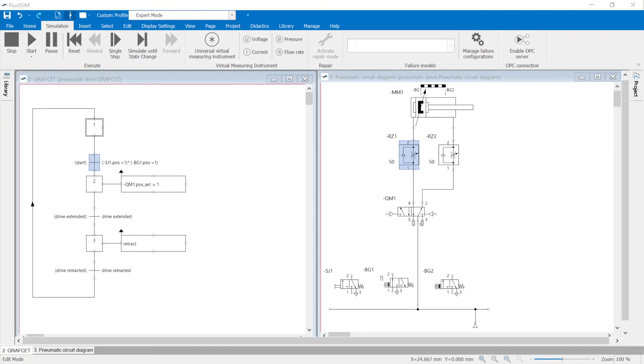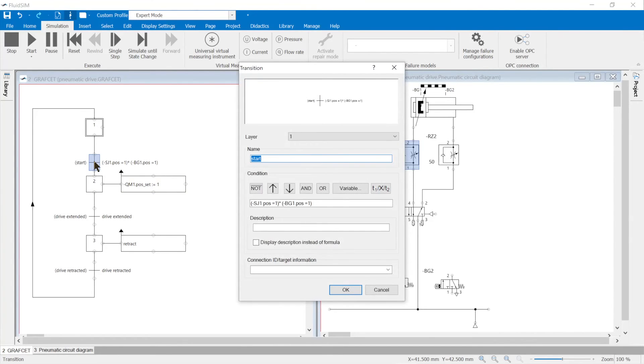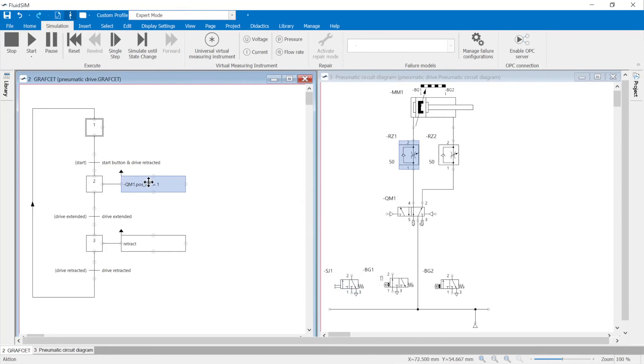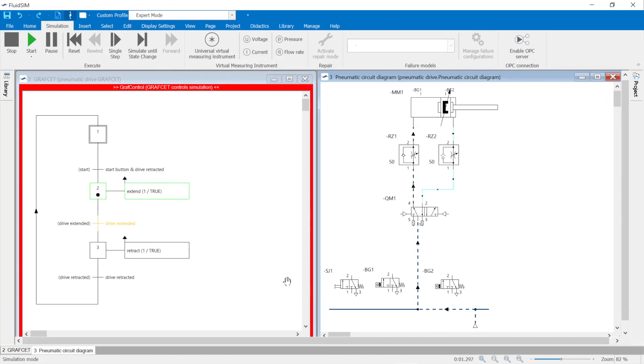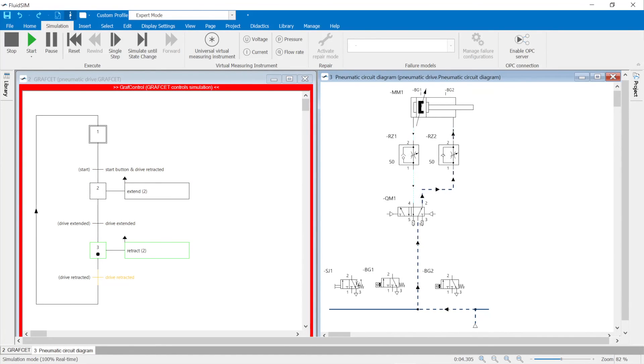GRAFCET technology neutral and simulatable: a technology-neutral GRAFCET cannot be simulated directly. However, the mathematical descriptions of the transitions and actions can be replaced by technology-neutral designations. In the dialogues of the transitions and actions, the formula can be replaced by a description. In the start transition, the start condition can be formulated as text in the description field. Additionally, the field 'show description instead of formula' is activated. If this is carried out in all transitions and actions, a technology-neutral GRAFCET is created that can be simulated.